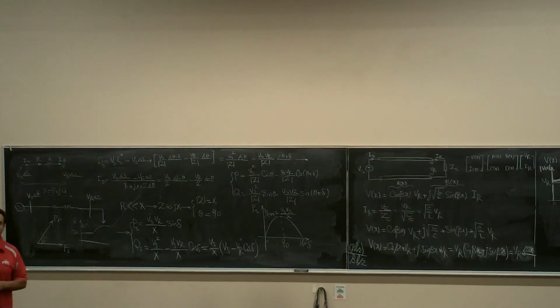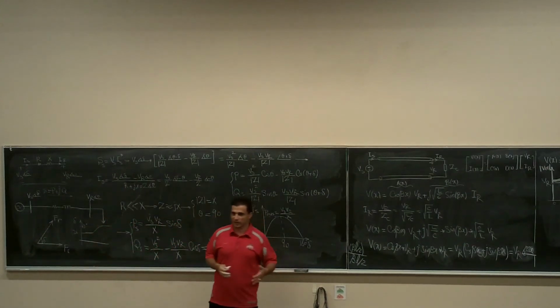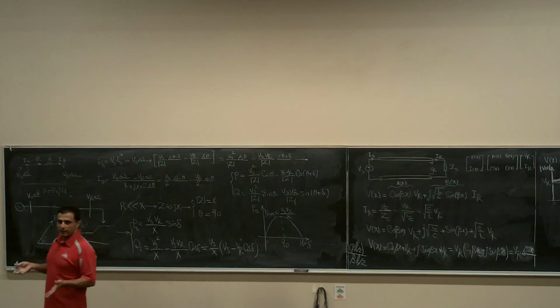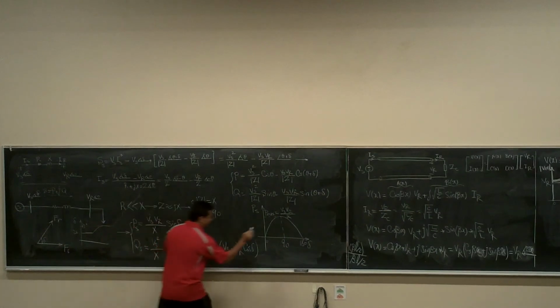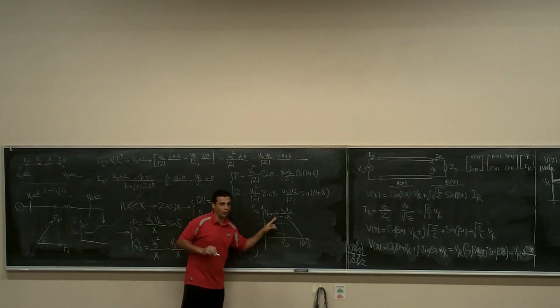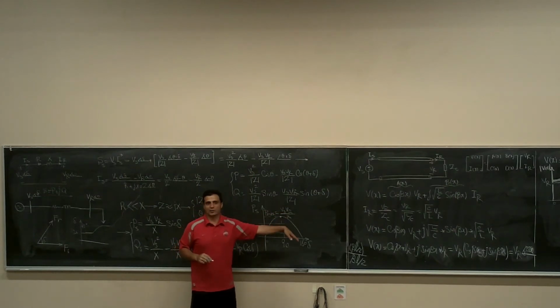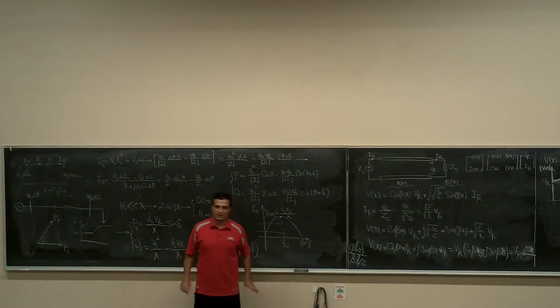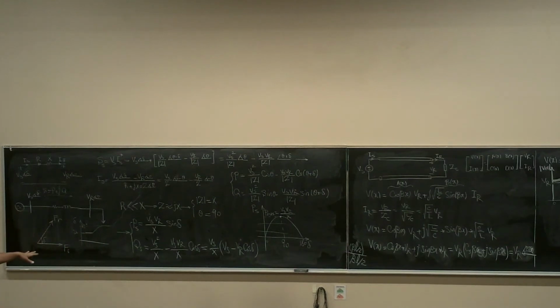They call it dispatching. Power dispatching is a very important part of power system analysis. If you go to SPGA and those kinds of things, the load management. You have to know how much load you have, and you make sure you are somewhere here. If the load comes in, you still have some space to go. You still have some reserve to cover it, right? If you design it for here, what's going to happen? Boom. As soon as you have a little bit more load, boom, you're unstable. Usually for a power plant generator, this delta is less than 30 degrees.